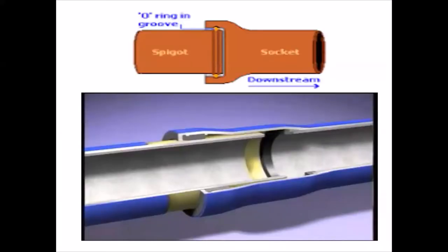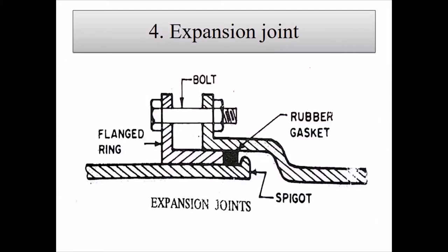The expansion joint is recommended for places where elongation or shortening of the pipe may occur due to changes in atmospheric temperature. The bell end projects vertically to some extent for coupling with a flange ring by nuts and bolts. The flange ring and rubber gasket are placed on the spigot end, which is then inserted into the bell end. The rubber gasket is pressed tightly in the annular space by means of nuts and bolts to make the joint watertight.